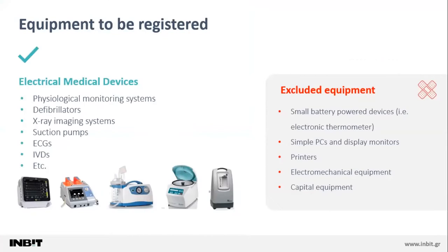It was also clarified to local staff — who would be called to repeat this registration procedure themselves in the future — which types of equipment to register. This includes electrical medical devices most likely to need repairs or periodic maintenance, like defibrillators, suction pumps, or X-ray imaging systems. Equipment to be excluded includes capital equipment, small battery-powered devices, or consumables.